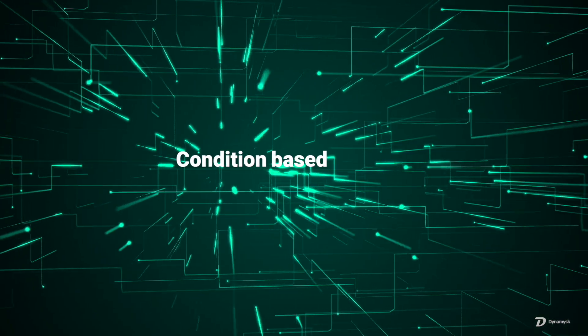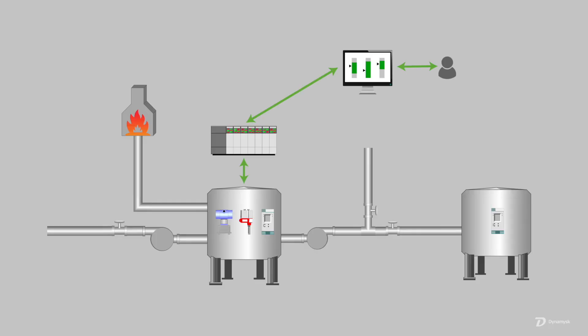How about condition-based controls? Operators are often faced with the same decision paths multiple times in process controls. To control a level in a vessel, for example, they may need to control the inflowing product and the outflowing product. To keep it simple, we'll say the outflowing product has two paths — one is to a flare and the other is to a vessel downstream. As the upstream vessel fills and reaches its optimum operating level, the outflow to the flare begins. When the downstream vessel or process is ready, the operator starts to close the flare control valve and open the control valve to the downstream vessel. It's fairly common in a startup scenario.